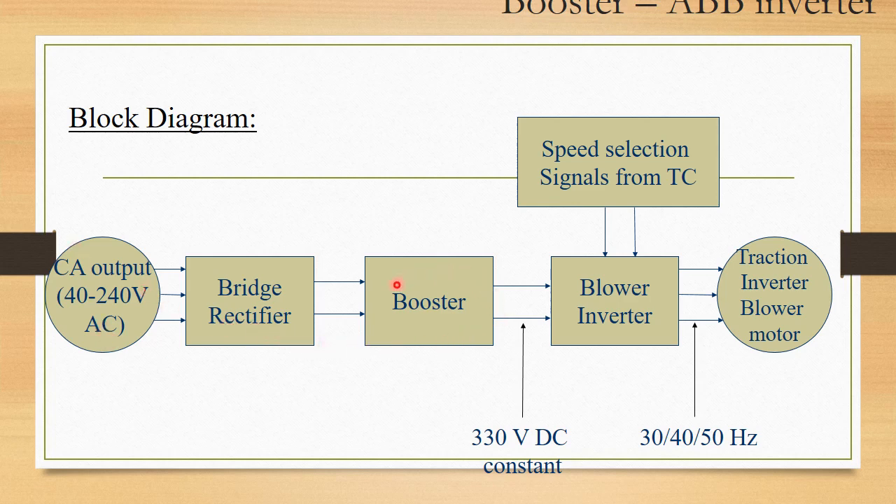The CA voltage is rectified in a bridge rectifier, and this DC voltage goes to a booster which boosts it to 330V DC. This 330V DC goes to the ABB inverter — the blower inverter — where it is converted to 3-phase AC for the traction inverter blower motors. The blower motor speed is controlled in 3 different speeds depending upon the temperature of the cabinet.